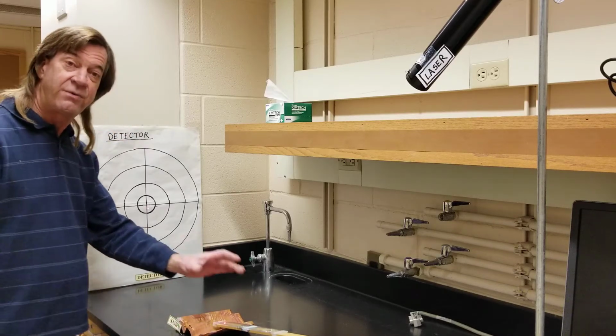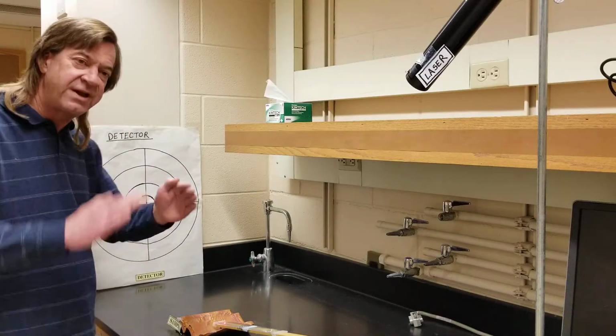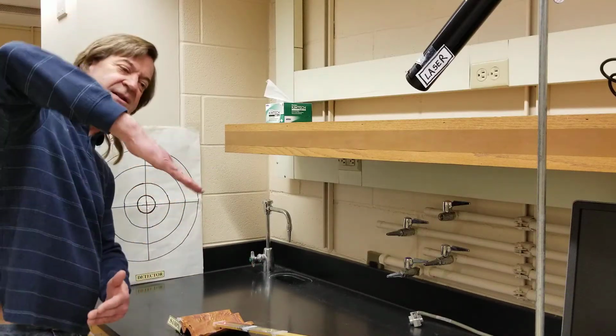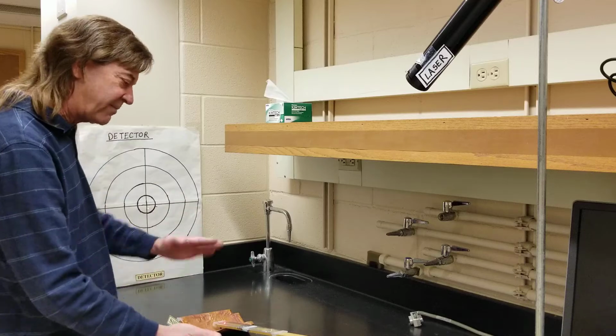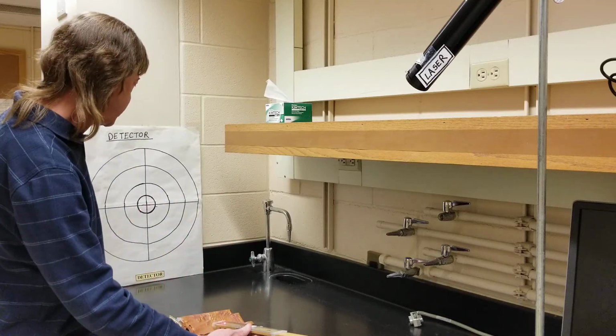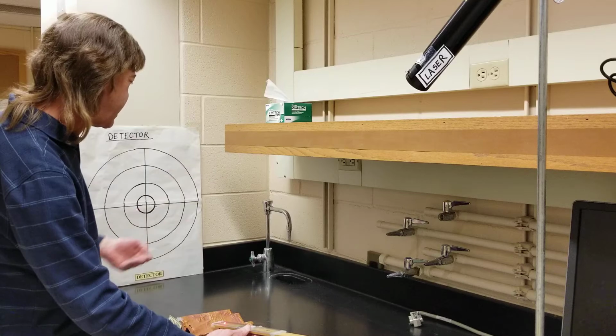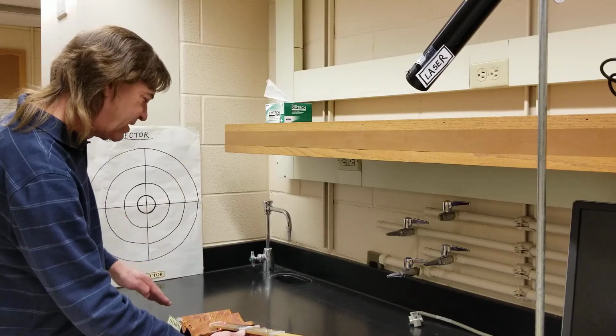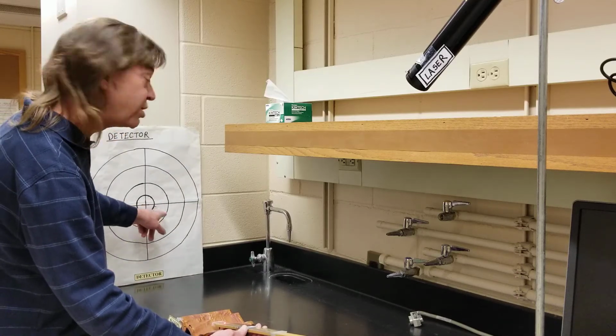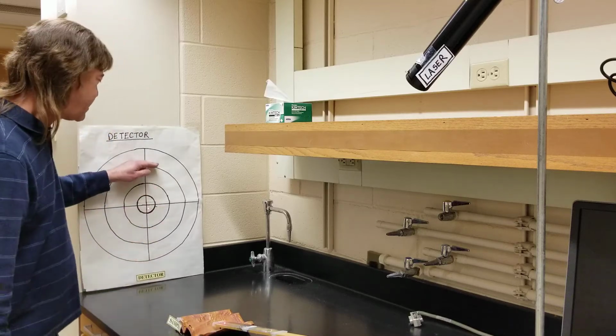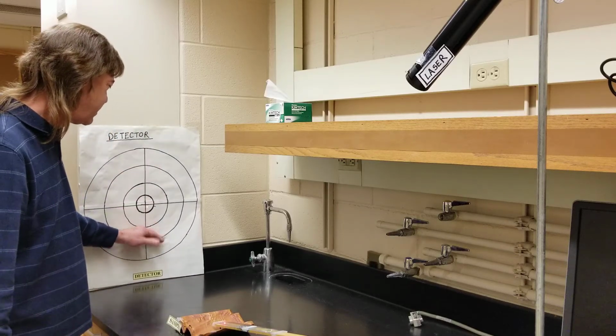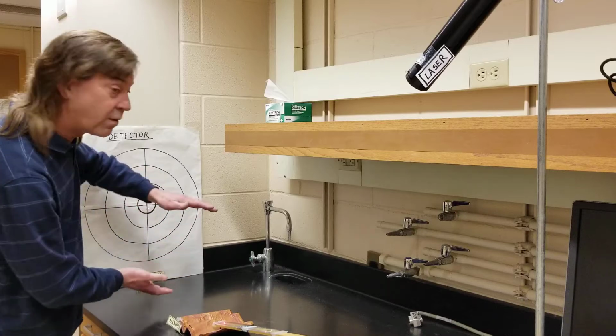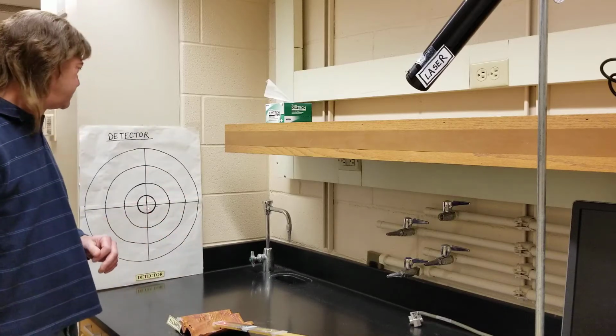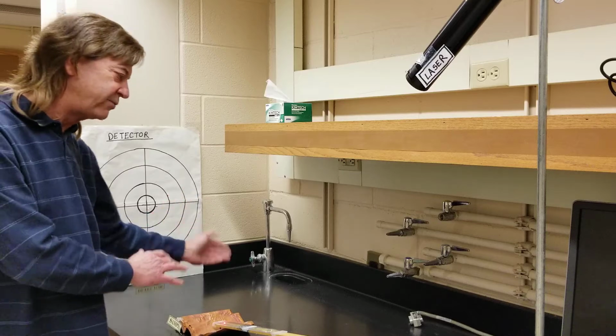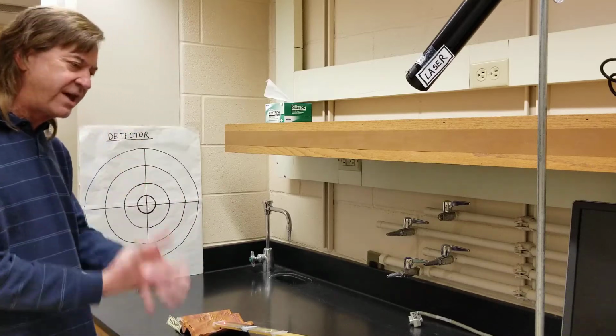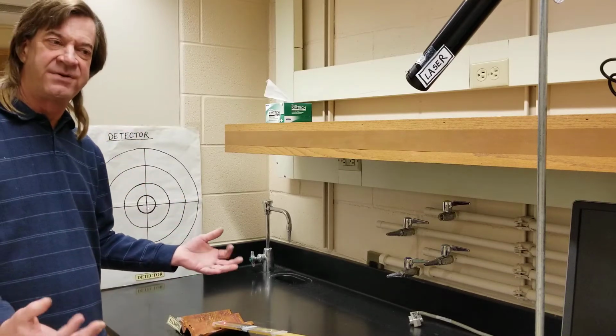Now, because these are so thin, not only will it give us heights, but it also gives us each data point a direction of slope. So if I had something that was angled like this, it would end up pushing over here. That'll indicate it's got this kind of angle. And if it was angled like this, it would rotate a little bit over on this side. So we have both height, high, middle, low, and a bend one way or another. Okay? So that's basically what it does. It simply scans, rasters across, gets all these data points, and then we put together the puzzle in the picture.